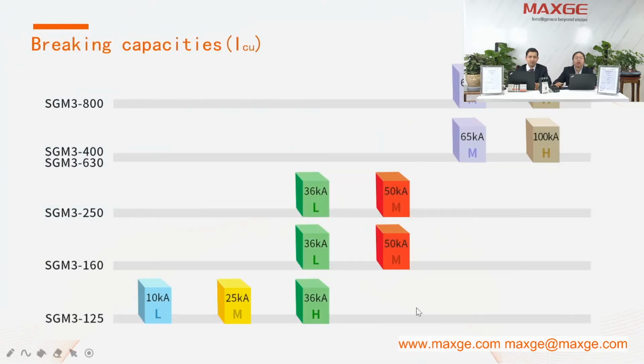Here are the breaking capacities, the tables for each frame of our MCCB. You can see here from 125, we have L type, M type, and H type. Some customers require a high braking capacity. Yes, we have a good range so that customers have flexibility in choosing the breaking capacities. So for the different breaking capacities, the 125 frame, the 400 frame and the 800 frame, this is in the same size, right? Yes.